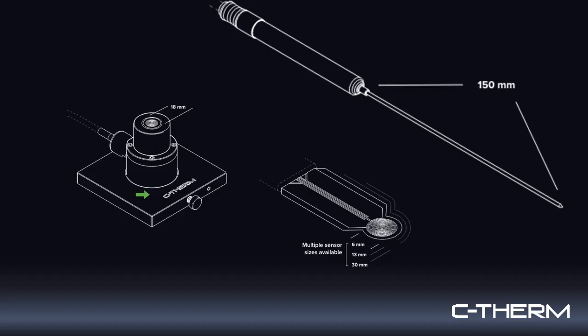So the needle probe is really oriented towards those very sticky situations. If you're dealing with a polymer melt, for example, something that might bond to these other sensors, then that's a situation where you're much better off having this kind of robust needle. It's not quite as sensitive and accurate because of that stainless steel sheathing that goes around it, but you gain a lot of robustness in that. And there's a lot of situations where that's a significant advantage.